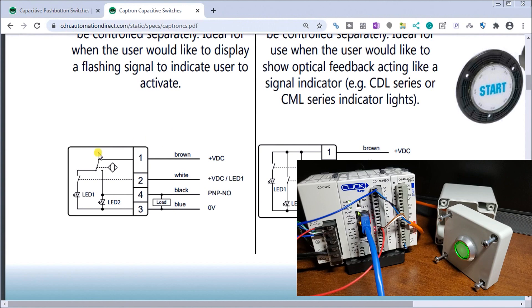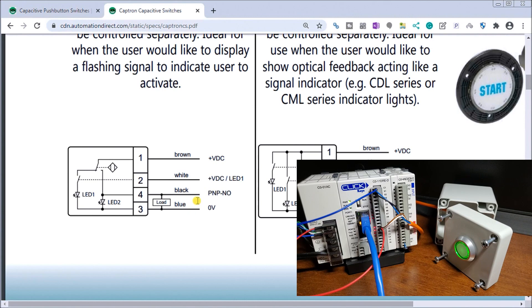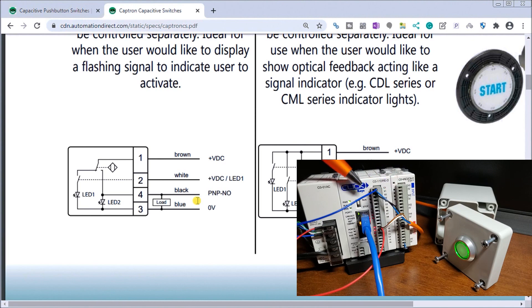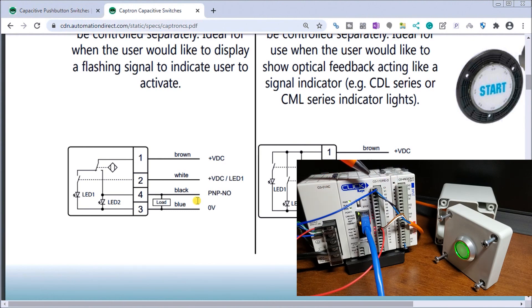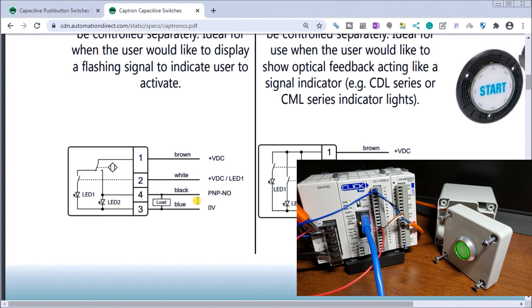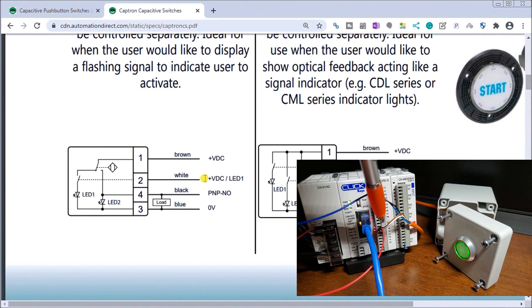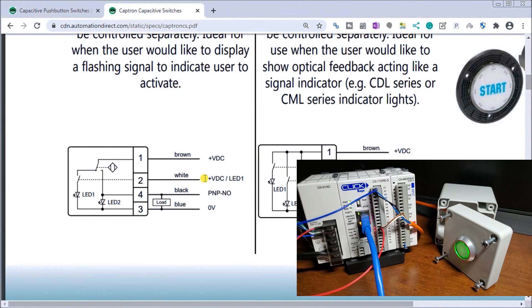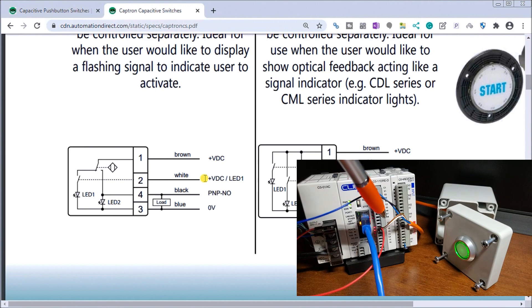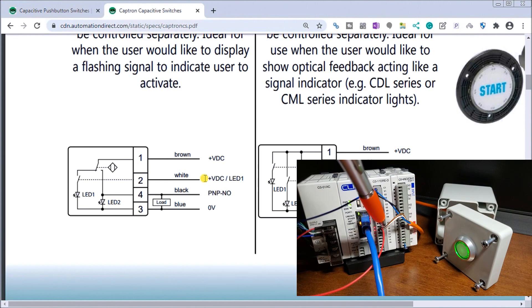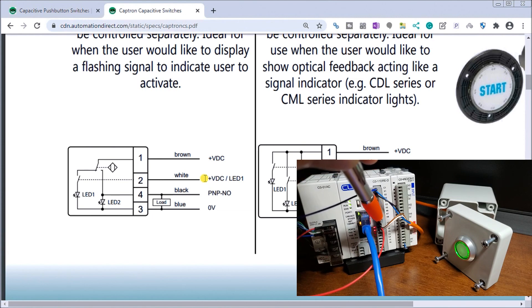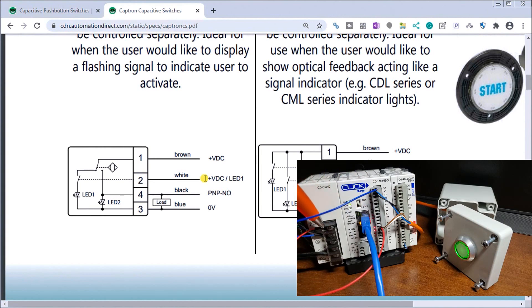So here's our wiring diagram and you can see that my load which is my PLC input is a PNP normally open and it's between the black and the blue wire. So the black wire as you can see here is actually going into my first input which is X1, then my blue wire is my common for that input which is going back to my zero volts DC. Then on my white wire which controls my green LED, it's going into Y1, and then the common is my brown wire for my outputs going back to plus 24 volt DC.